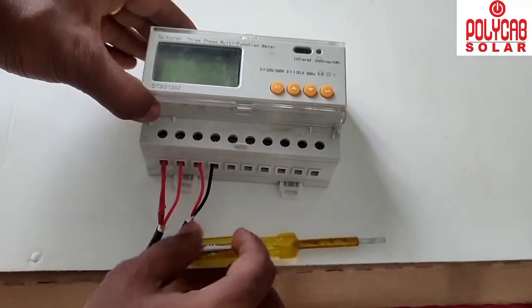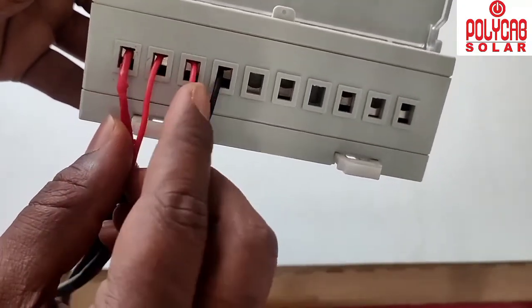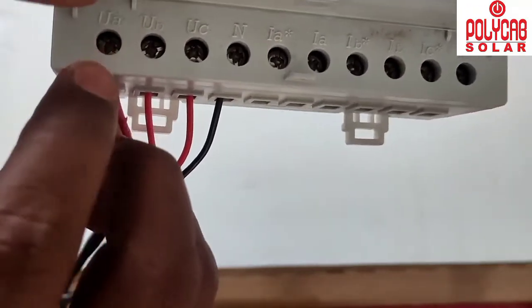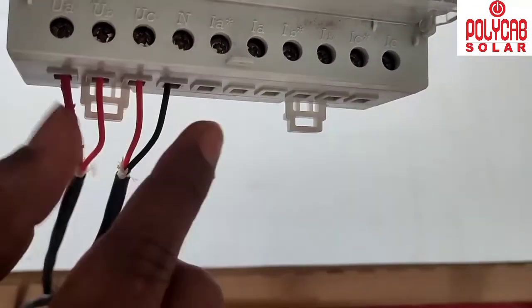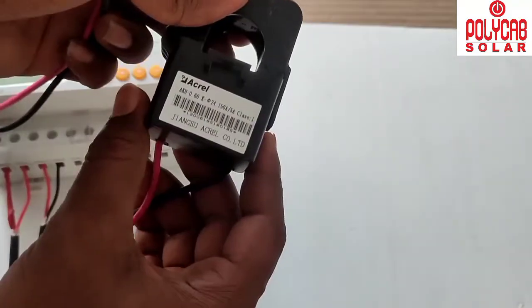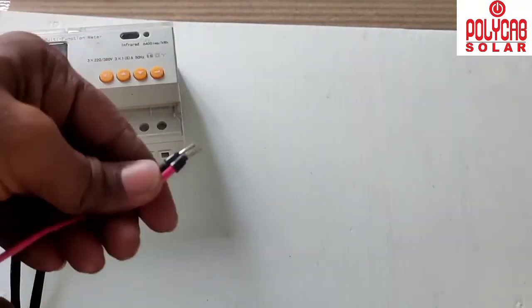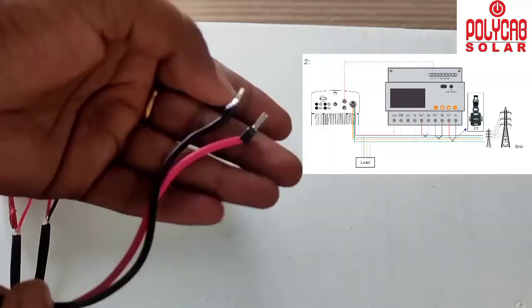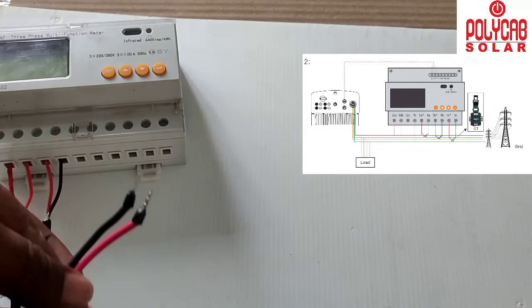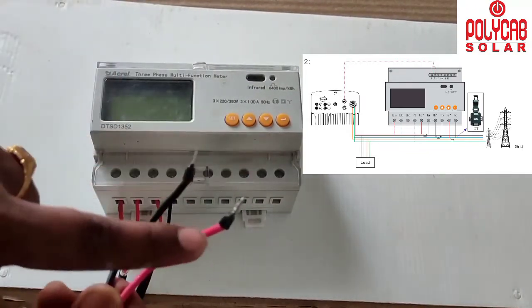The three-phase supply and neutral connection is now done properly — Ua, Ub, Uc and neutral are all connected as required. For the CT coils, each coil has two cables: one red and one black. These must be connected according to the connection diagram provided for the zero export meter.